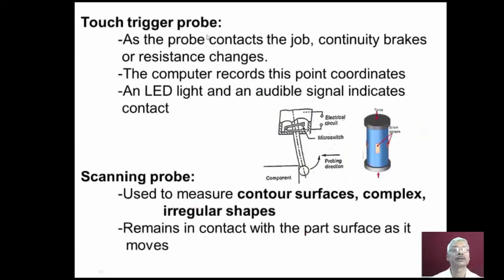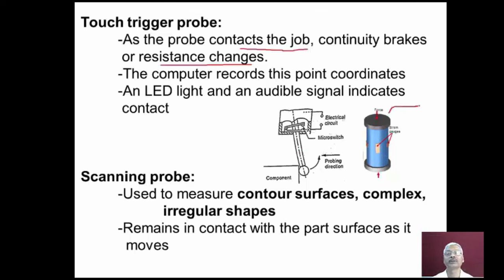In the case of a touch trigger probe, as the probe contacts the job, the continuity breaks or resistance changes. If it is a probe with a micro switch type, the micro switch gets opened and the signal is sent to the CMM software. If it is a probe based on strain gauges, when the probe deflects, the resistance of the strain gauge changes and hence the signal is sent to the software. The computer records this point's coordinates whenever the probe comes in contact with the component. An LED light and an audible signal indicate the contact.